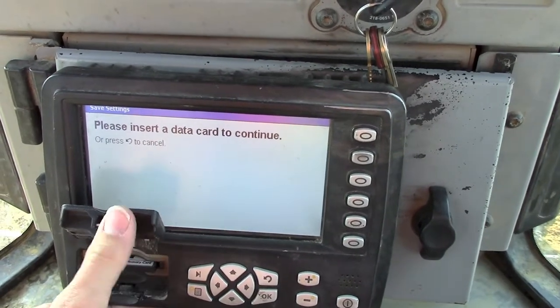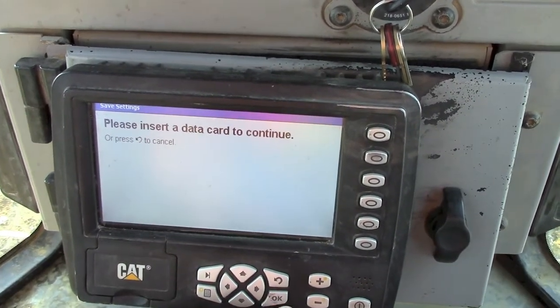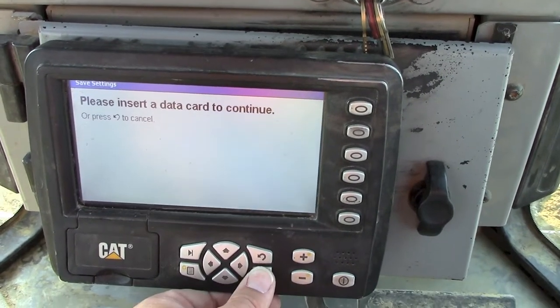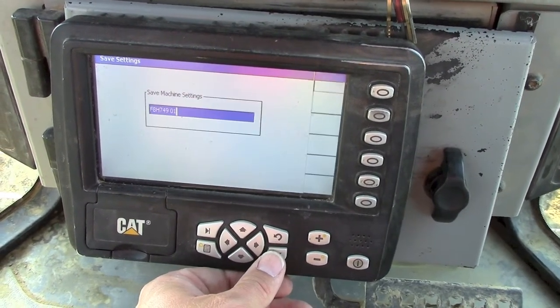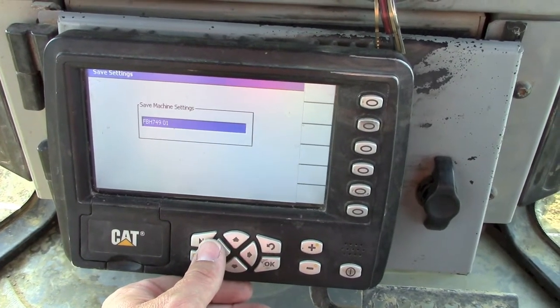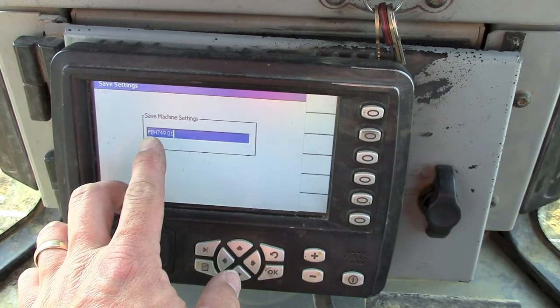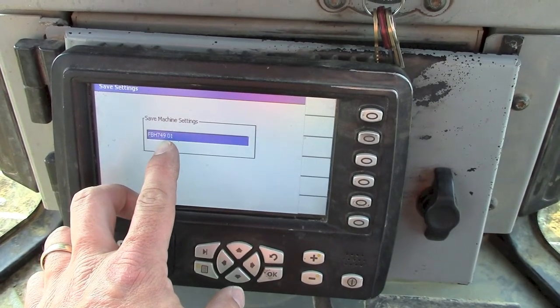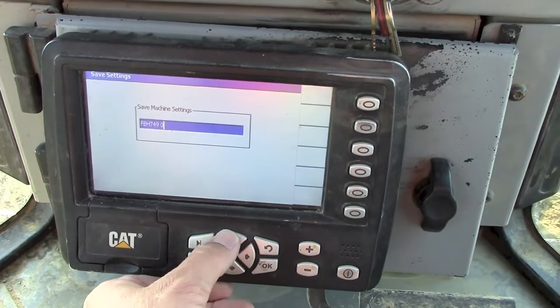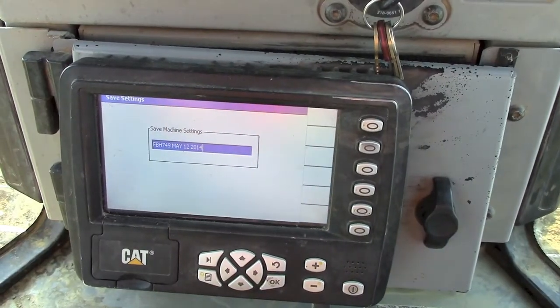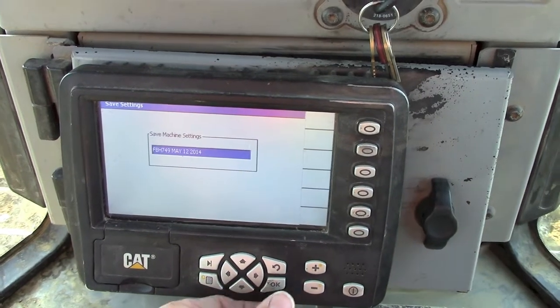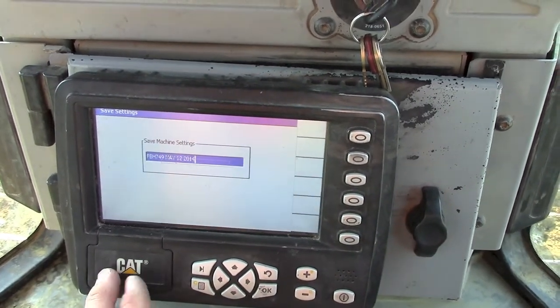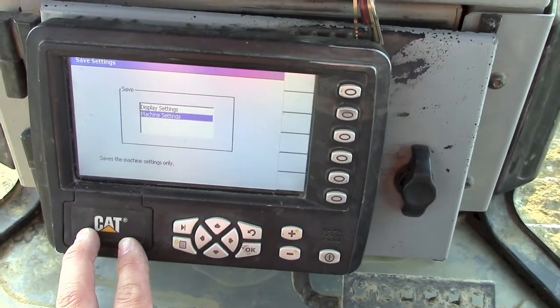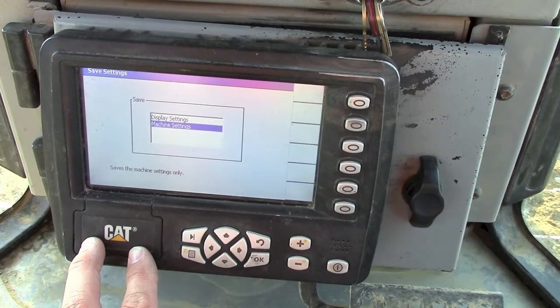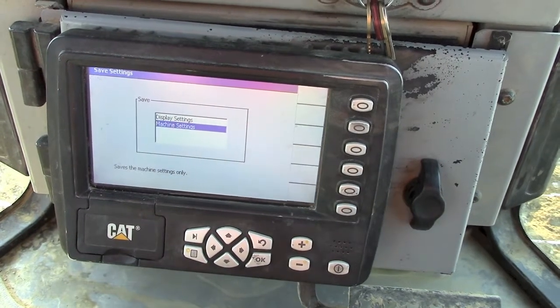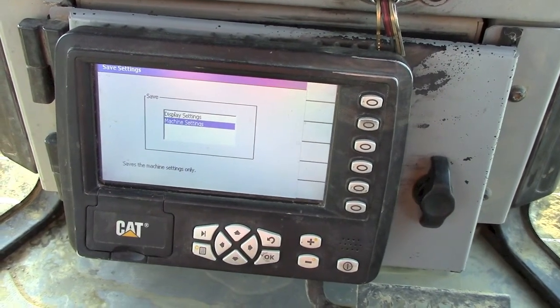Do need to make sure that the data card is inserted. And we could give it a name. It comes up with a default name of the name that we've given the machine, in this case FBH74901. We could change that 01. I will now be saving it as the machine serial number with today's date. That will be saved only to this data card, so it may want to be pulled off, put on to a server or some other type of a hard drive for archival purposes. But we now know that that file contains the latest valve calibration to date.